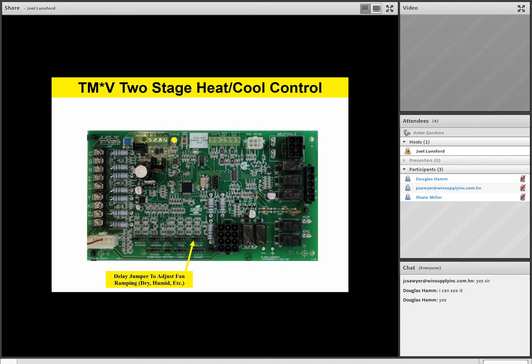So that ramping profile on that fan really starts pulling extra moisture out of the air on that initial call for cooling. And so the delay profile, just please make a note of this, this is a cooling on delay profile, and based on your geography, you can ramp that fan accordingly.